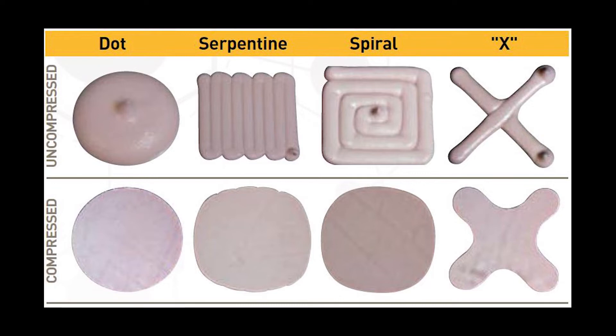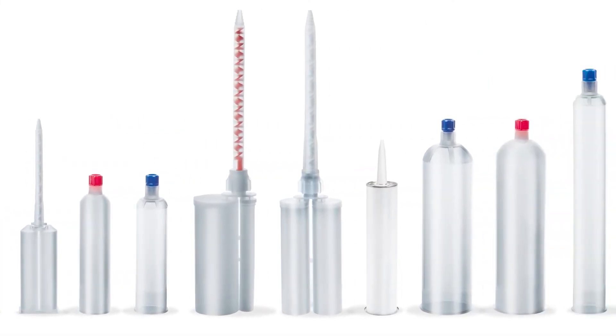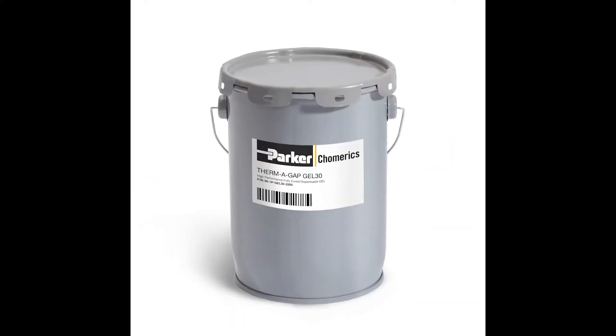It's also important to ensure proper surface roughness, which helps the material wet out for better thermal performance and long-term reliability. Dispensing technique, shot size repeatability, and proper application method are additional critical considerations. Our gels and putties come in a variety of packages: 10-cc manual syringes for sampling, 30-cc syringes, up to 20-ounce cartridges, and even one- and five-gallon pails for larger applications.